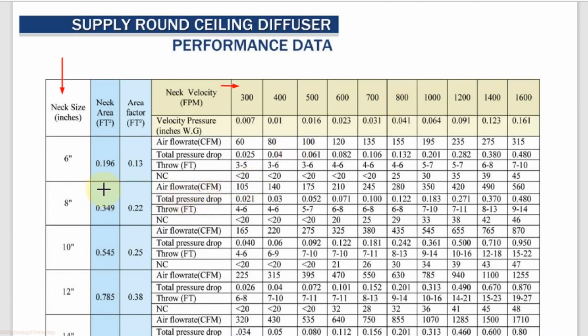For each neck size there is a sub-row. In this sub-row there is airflow in CFM, total pressure drop, total throw in feet, and NC level. From this sub-row, you need to select the CFM as per your requirement and NC level, then select the corresponding neck size at the corresponding neck velocity.